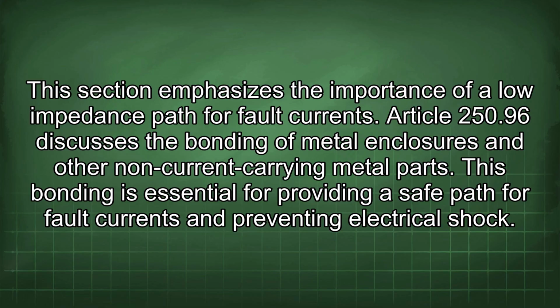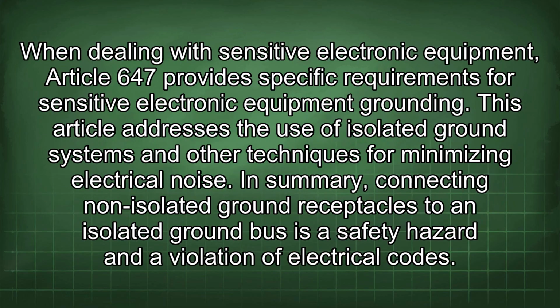Article 250.96 discusses the bonding of metal enclosures and other non-current carrying metal parts. This bonding is essential for providing a safe path for fault currents and preventing electrical shock. When dealing with sensitive electronic equipment, Article 647 provides specific requirements for sensitive electronic equipment grounding. This article addresses the use of isolated ground systems and other techniques for minimizing electrical noise.